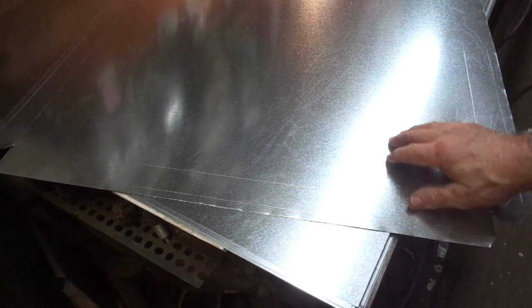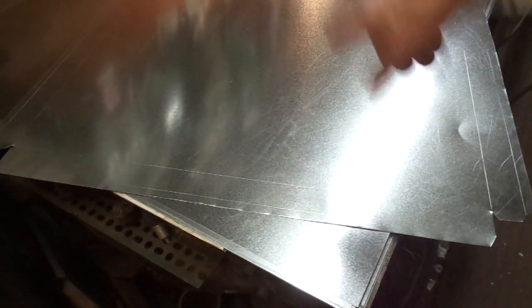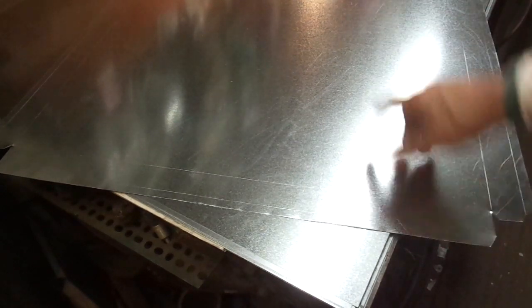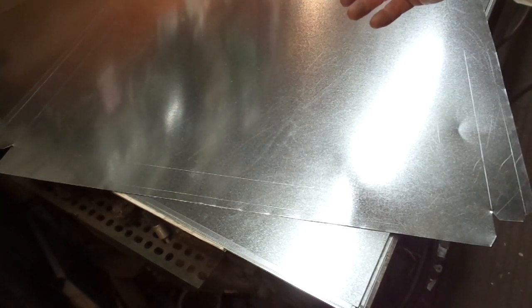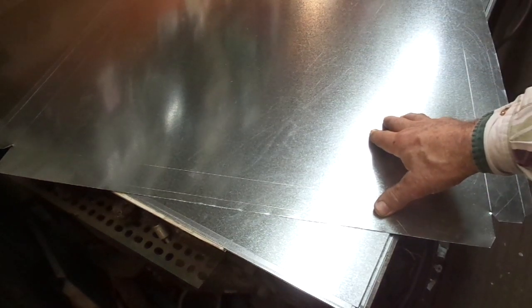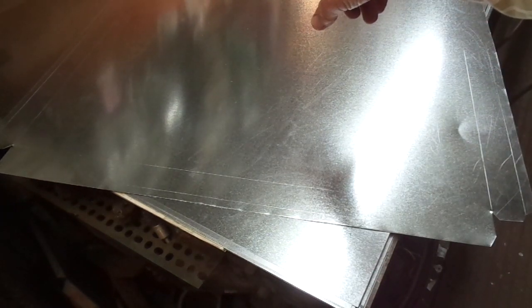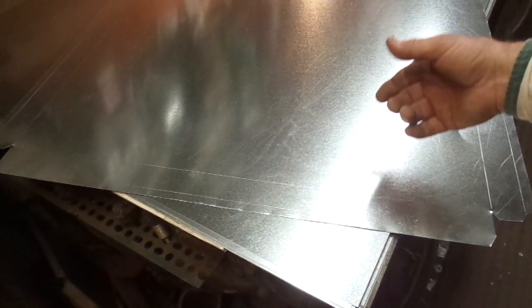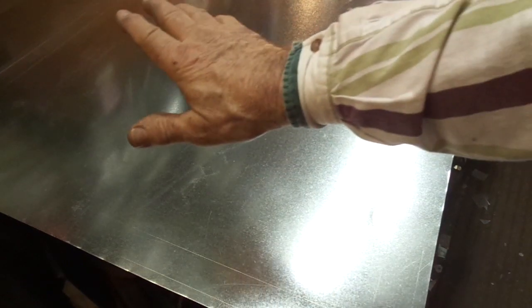Now what I'm going to do on this is I'm going to put one cross break, just cantywampus from one corner to the other corner, and not an X brace. If I make an X cross brace and the drain pan starts collecting water because of an overflow in the air handler, it'll collect in the middle and it'll take a lot longer for you to be aware that there's a problem with the drain. So I put them cantywampus across one corner and then put the float switch in the lower corner, and so any dripping will run to that corner and set your float switch much more quickly than if it has to fill up from the middle and go to the outside edge.